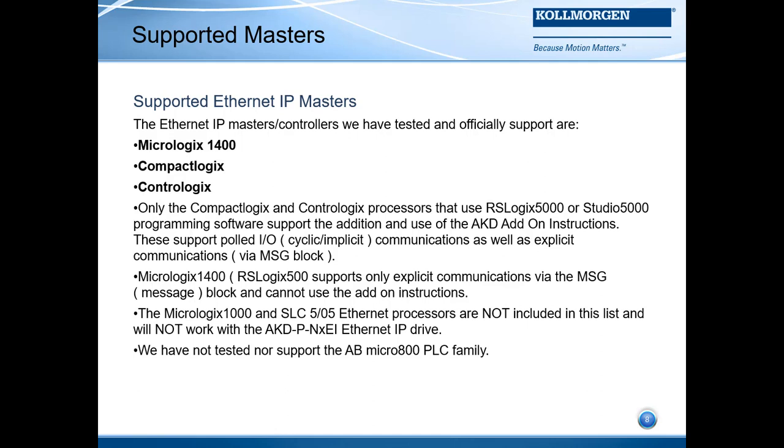Only the CompactLogix and ControlLogix processors that use the RSLogix 5000 or Studio 5000 programming software support the addition and use of the AKD add-on instructions that we supply. These support polled I/O, cyclic, implicit communications as well as explicit communications via the MSG block.